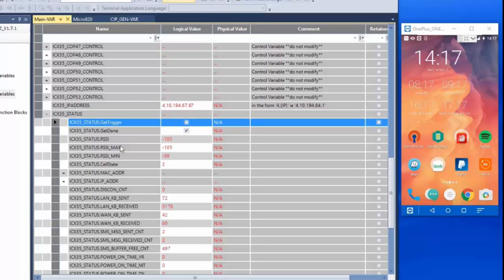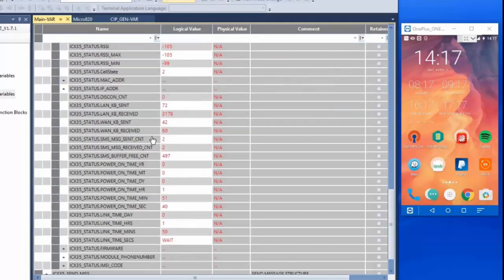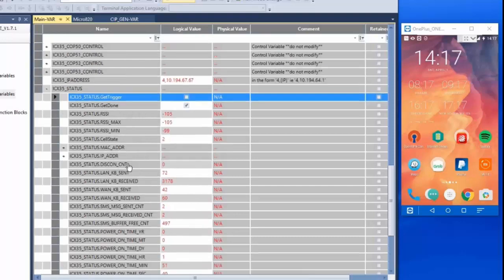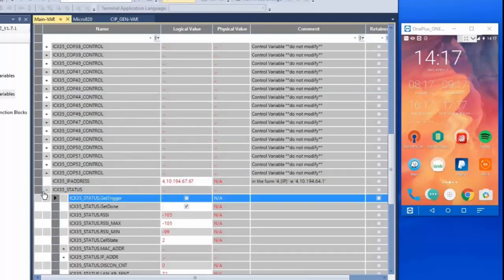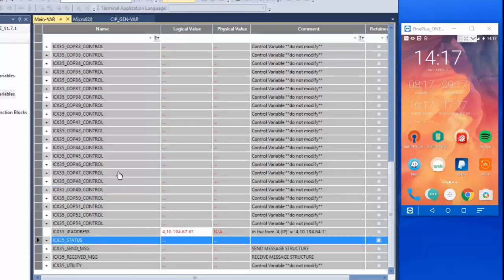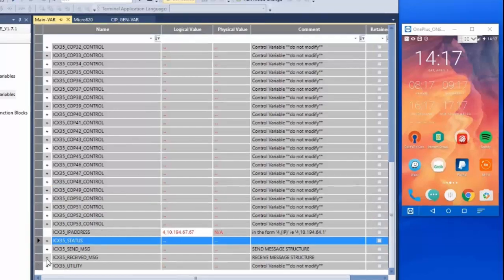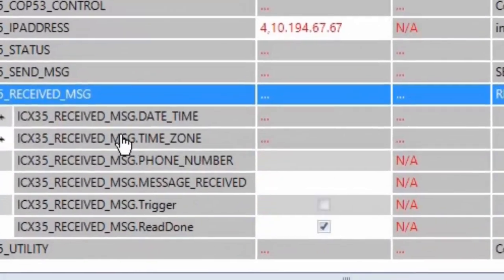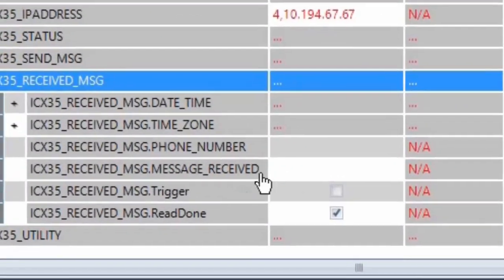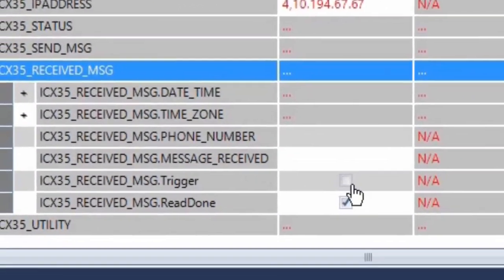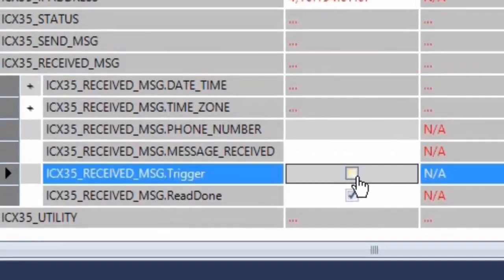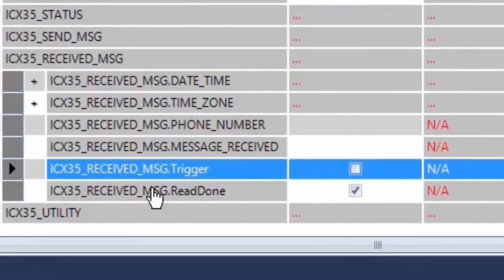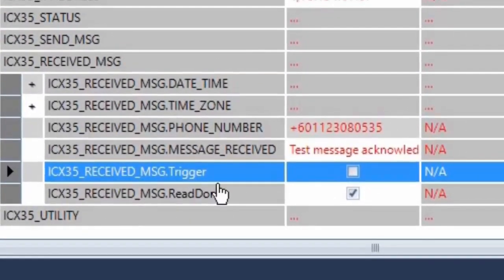Something to note, as messages are received by the ICX35 it does not simply send them on to the controller. They're actually stored in a buffer on the gateway. So to get the reply messages in the tags we must send a high signal to the received message trigger boolean tag.